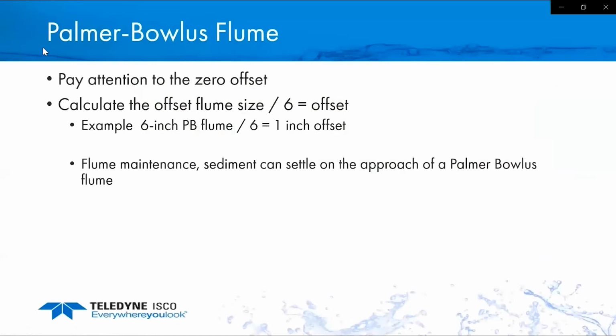So to determine what the offset is, you can determine the size of the flume. So if this was a 6-inch Palmer-Bowlus, I just take the 6-inch divided by 6, and then that gives me a 1-inch offset. So if we measured that overall depth of 4 inches, subtract 1, the level calibration would have been 3. Now keep in mind, because it does have that little offset, you could have sediment in front of that flume, so it may be a maintenance issue that you'd have to go out there quarterly to clean it.